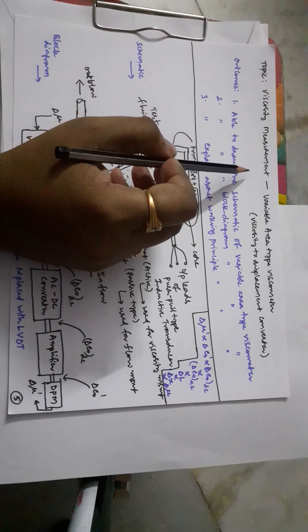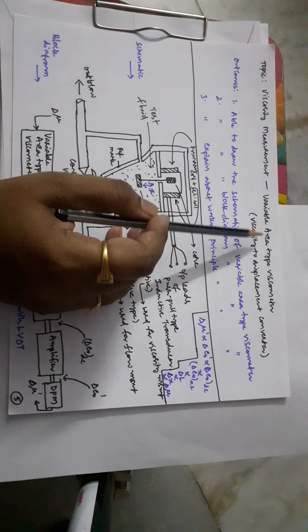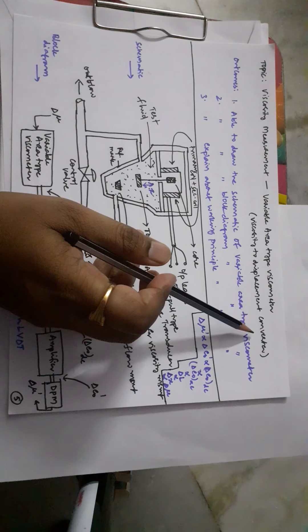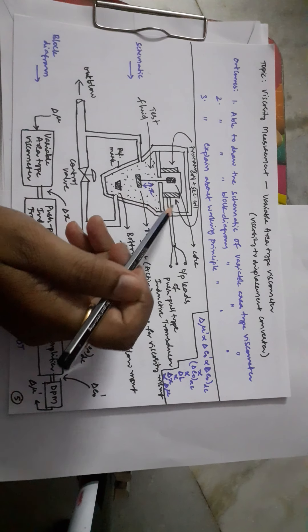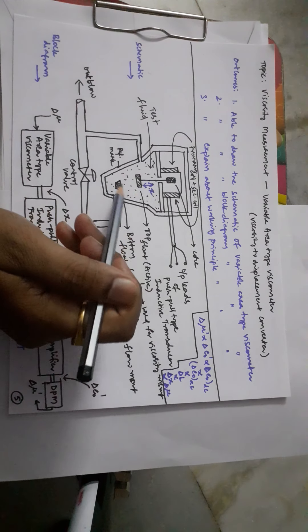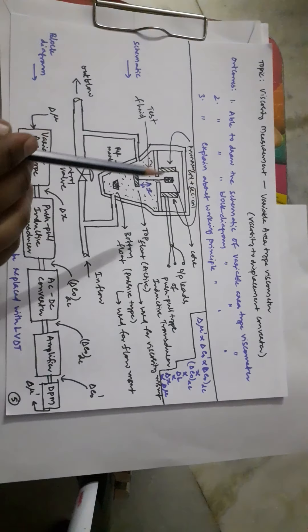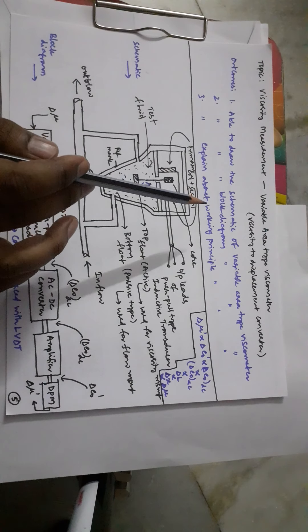In the previous video we saw viscosity measurement using a capillary viscometer. In this video we will see viscosity measurement using a variable area type viscometer, also called a viscosity to displacement converter. Its schematic is similar to the rotameter studied for flow rate measurement, and it converts viscosity energy to displacement energy.